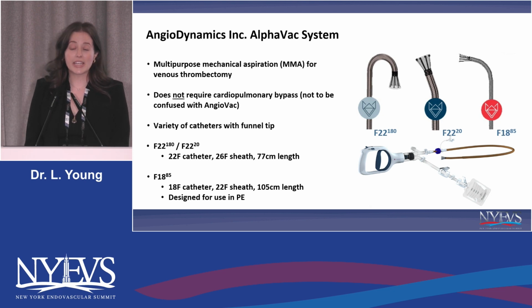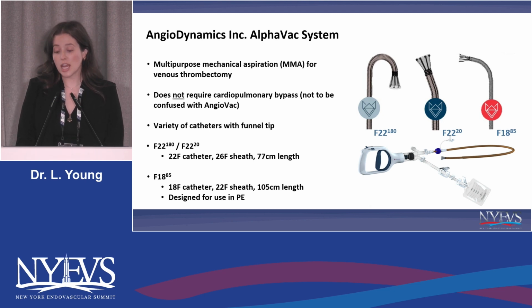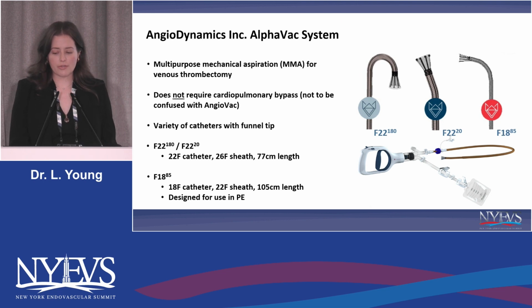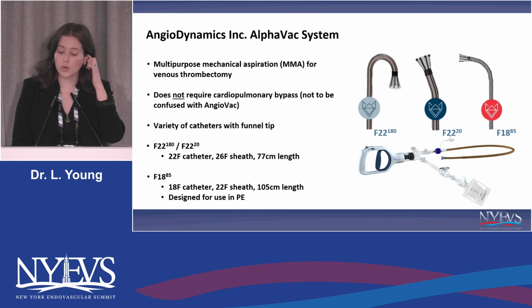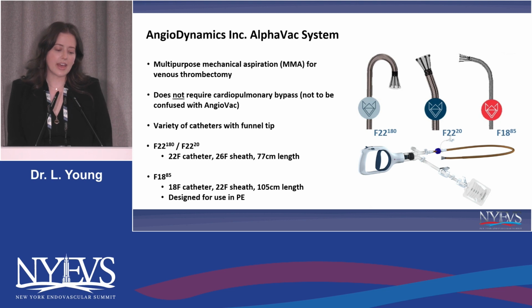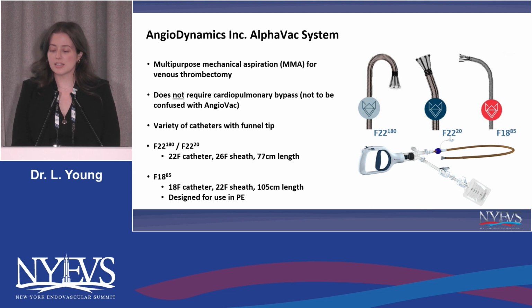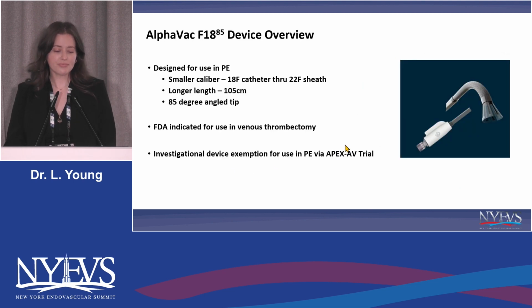It comes in a variety of catheter sizes and shapes. The catheter that they just used for the SVC case is the middle catheter you can see here. That's the 22 French catheter with a 20-degree angulation. The other 22 French catheter has a 180-degree tip, which is commonly used in cardiac thrombectomy, for example. These larger bore catheters are typically used for larger venous thrombectomy: IVC, iliacs, atrial, clot in transit, for example. And then the newest catheter, on the far right, is the 18 French catheter, which was designed specifically for use in PE, which I'm going to be talking a little bit more about today.